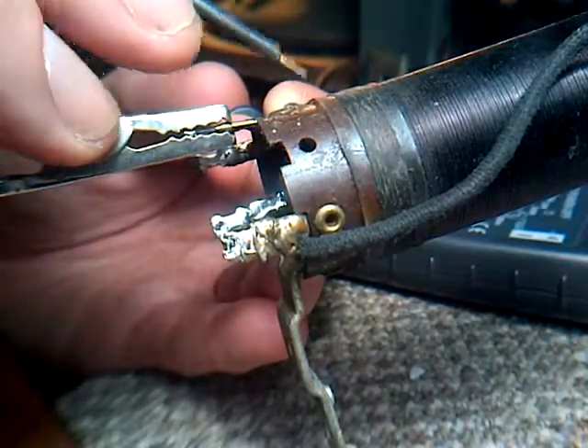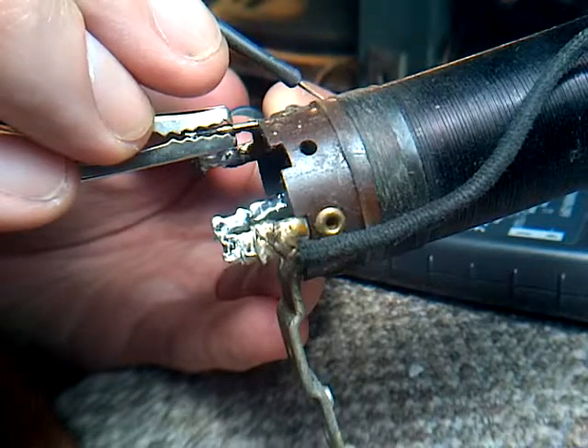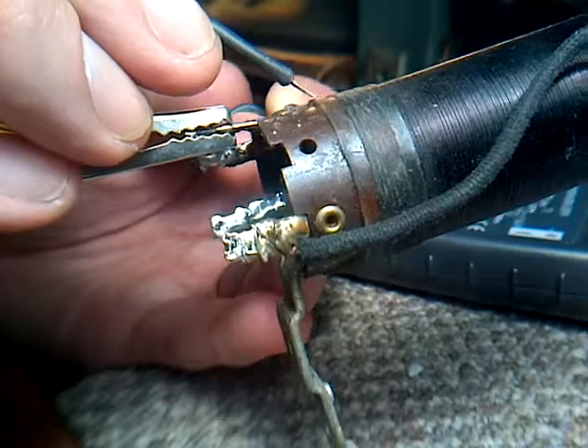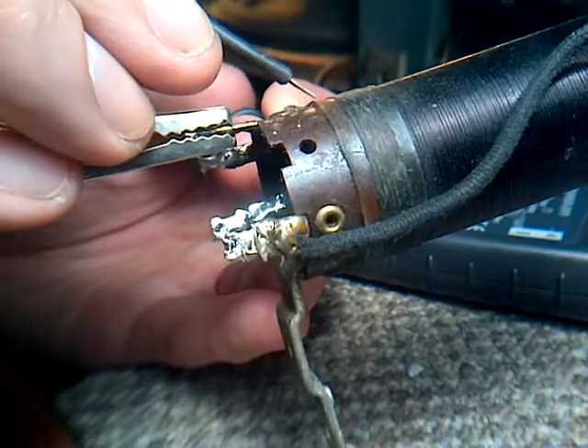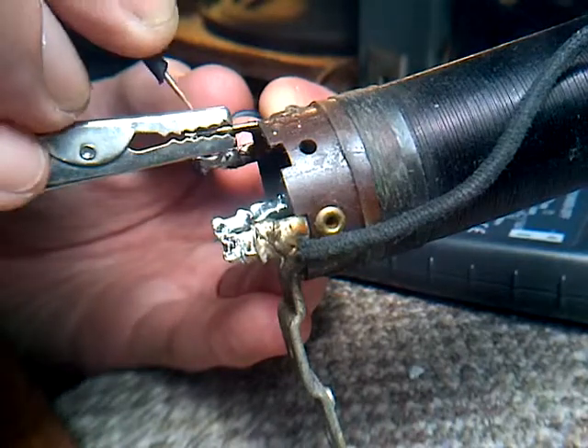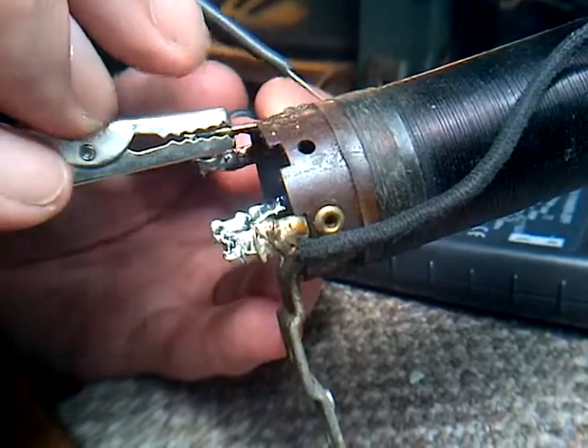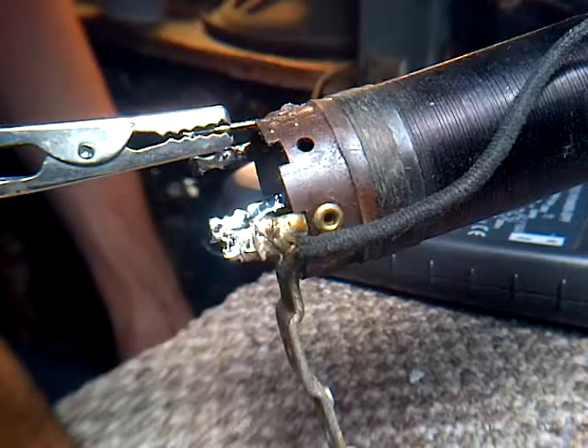What I'm doing is I believe I have one lead in contact with a bare point on that lead wire up high, right near the coil. I'm trying to prove that by contacting a second point just a fraction away. I think I've contacted the wire — I saw a reading. So that's proving the lead wire from the coil down to the other terminal. I've proven both leads are good, so that only leaves the coil itself.